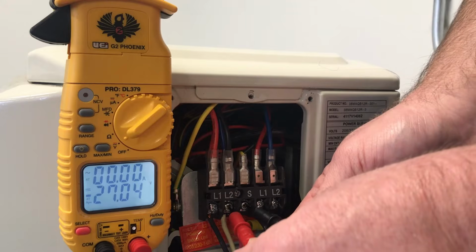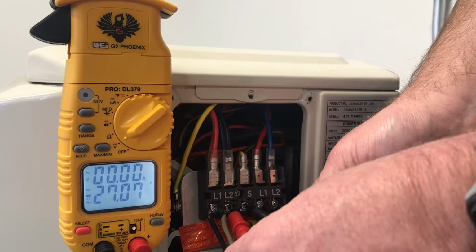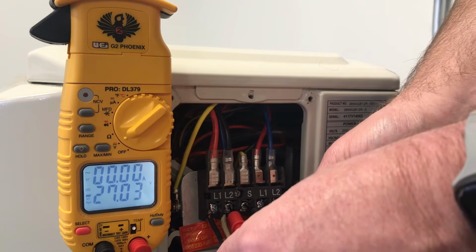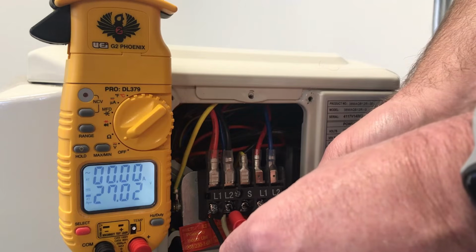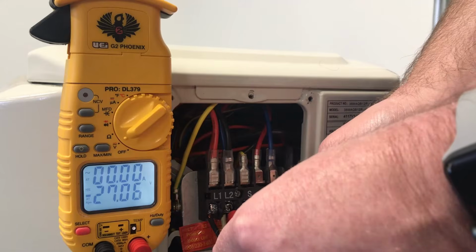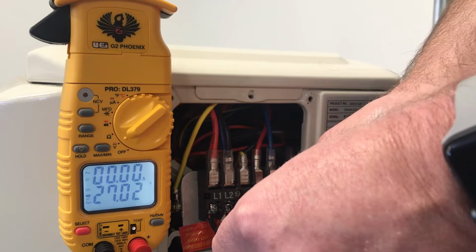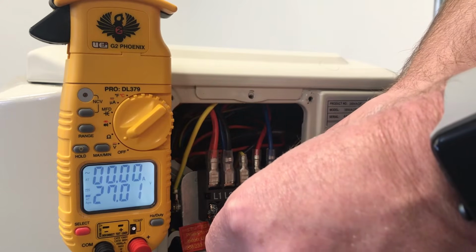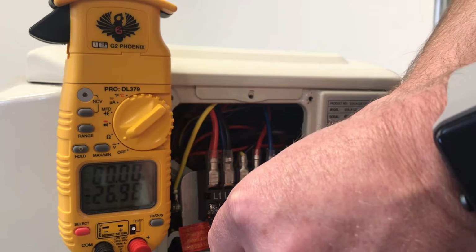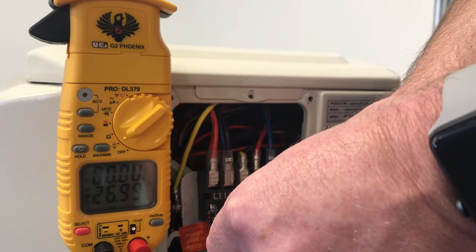And now if you notice, we have a steady negative voltage on our meter. Earlier we had a fluctuating positive only voltage. So that's telling me that my outdoor board is okay, but I am not getting the signal from my indoor board. So now that leads me to look at our indoor board over our outdoor board, or the wire between the two of them. So let's go inside and take another reading to see if the wire is bad or if it's a possible indoor board issue.